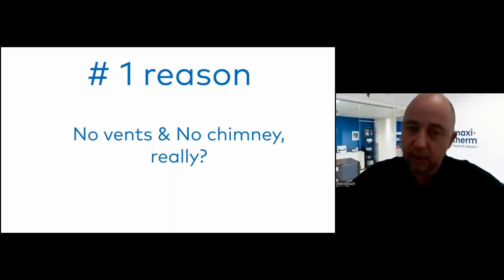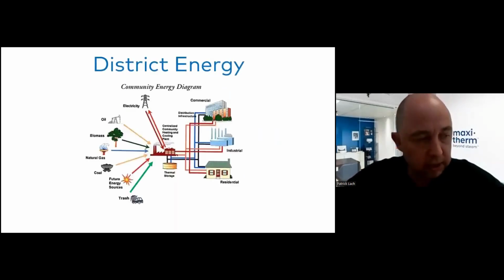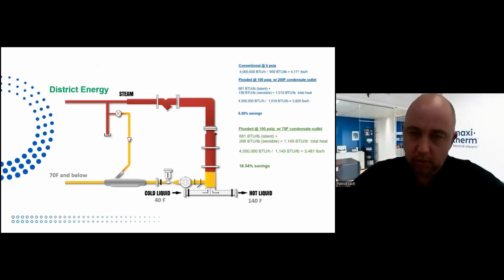Well, like I said, district energy, you bring steam in any building, you use a vertical flooding design, zero on-site combustion, so insurance costs are lower. No chimney, no gas vent, no steam vents. A reminder of those numbers from earlier. No quencher, so no fresh water needed to quench the water when you're dumping condensate to drain.